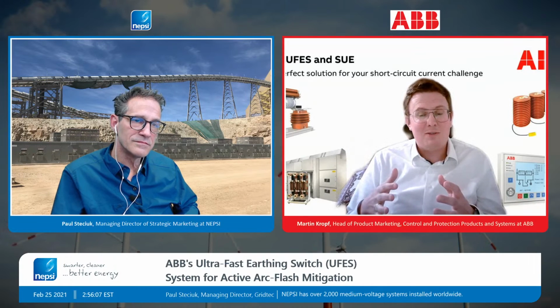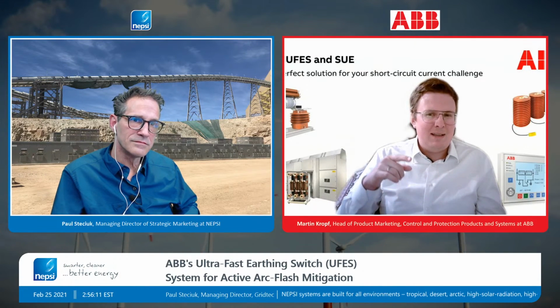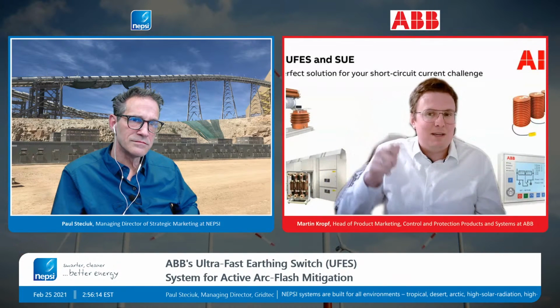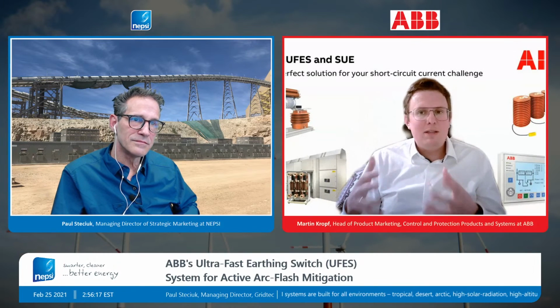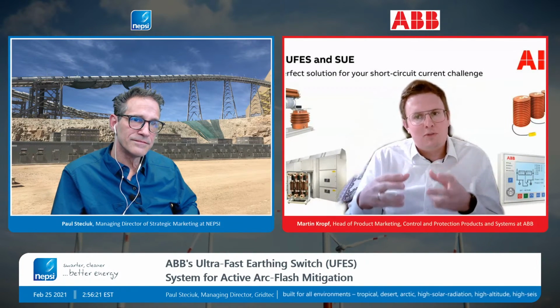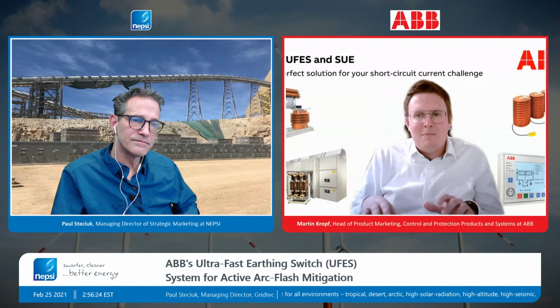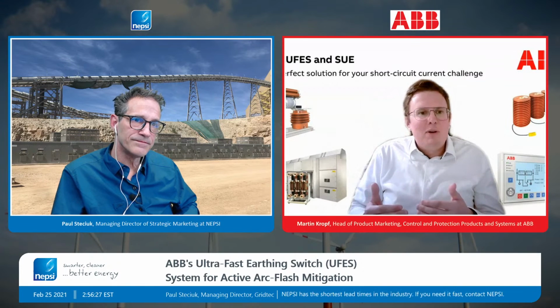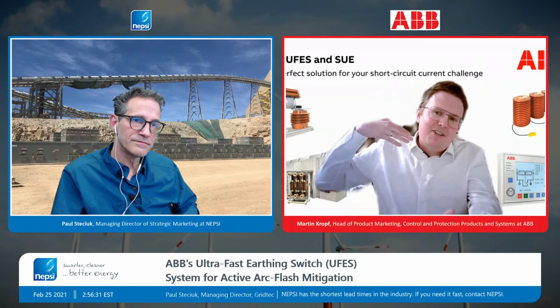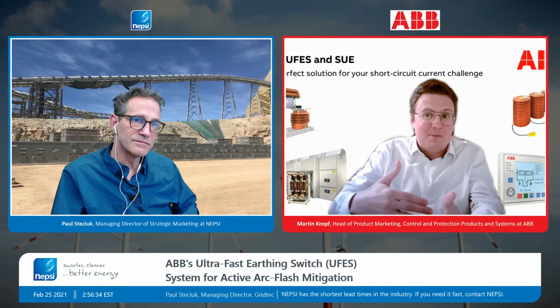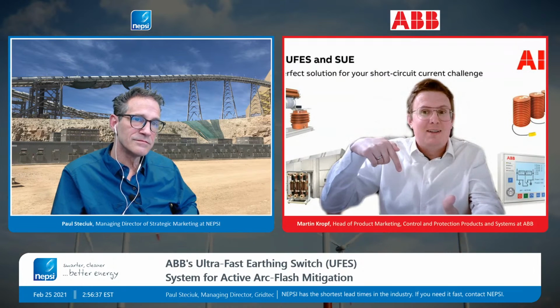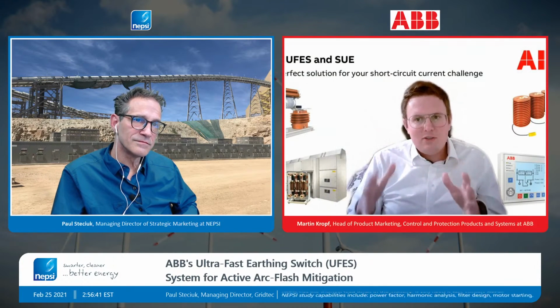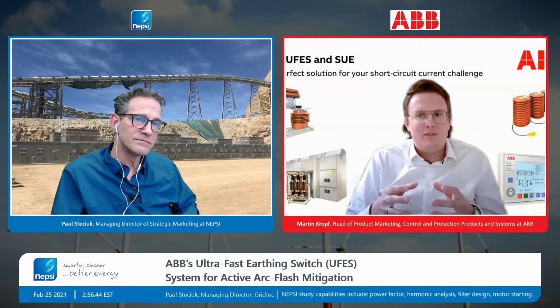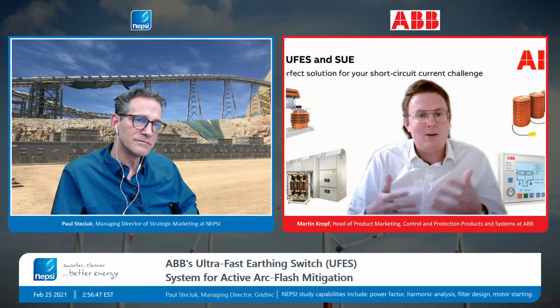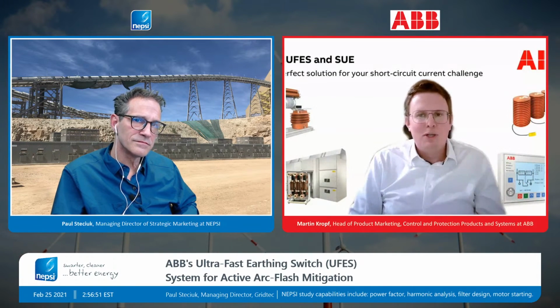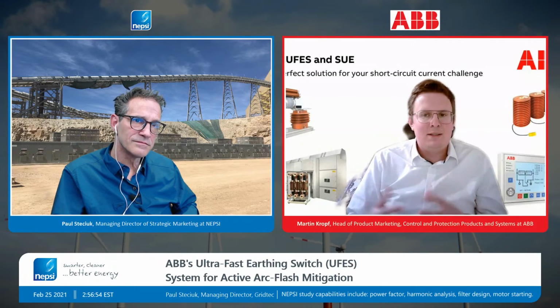We had some applications where the customer said, I don't want my utility to trip, because if they trip, they send me a check. So then we can look into this and redesign and put the UFES in a different position. To put it really at the entry is maximizing the protection zone, because if you put it somewhere in your gear, from the energy entry to the UFES there is no protection, because if there is an arc, you will not shut it down, right? So we always have to consider the protection zone, and then also really discuss this in the application. I don't know how you have done it in this big gear, which is behind you, how this was maybe a topic, and yeah, exactly.